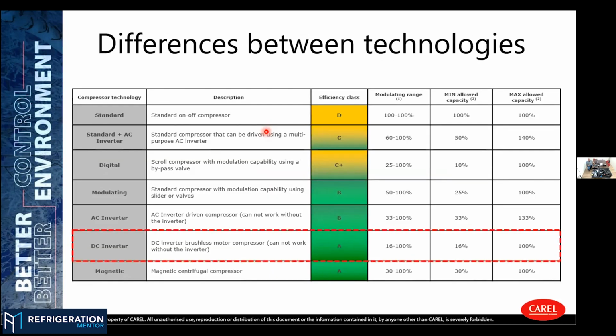And here, a very quick comparison between the different types of technology. You can see that we are in a very good shape with this inverter technology. We are just not as good as magnet ones, but magnet has its own limitations in terms of applications and capacities. They are very big compressors and rated for high temperature applications, not for medium and low temp applications.